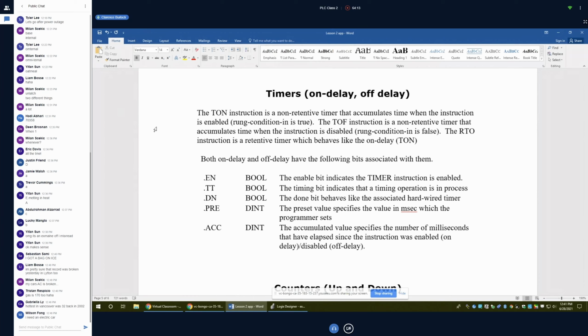Okay, so on-delay timers from second year and third year probably. On-delay timer, when we energize the coil, the contacts will time themselves either closed or open, depending if they're normally open or normally closed. So that's an on-delay timer. That one is fairly easy to understand. You energize the coil, then the timing action happens, then the contacts change state.